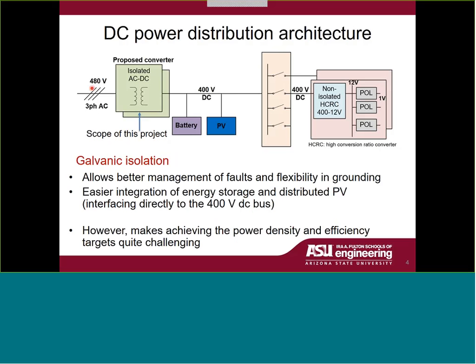This is the scope of the project, going from 480 AC to 400 volts DC. This DC is distributed throughout the entire length of the data center over long distances, and then near the point of consumption it gets converted to 12 volts, with point-of-load converters on the processors converting it further to 1 volt and below.